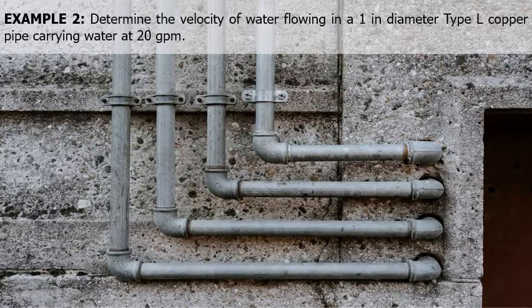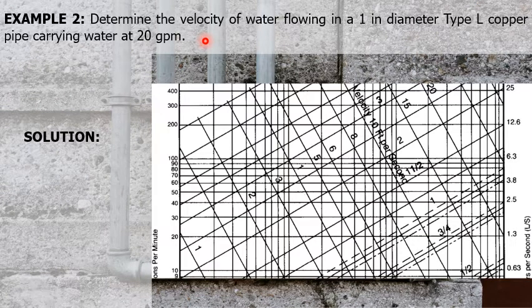Second example. Determine the velocity of water flowing in a 1-inch diameter type L copper pipe carrying water at 20 gallons per minute. This problem is similar to the previous one, except that here we're looking for velocity, whereas in the previous one we're looking for pressure drop. But still, we're going to use the same pressure drop chart, Figure 13.6. This velocity in the pressure drop chart is represented by diagonal lines slanting downward from left to right.